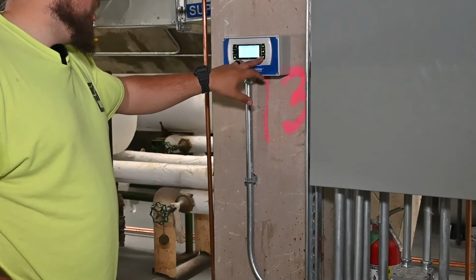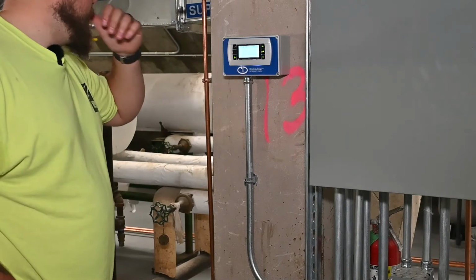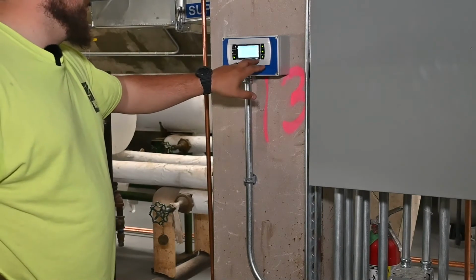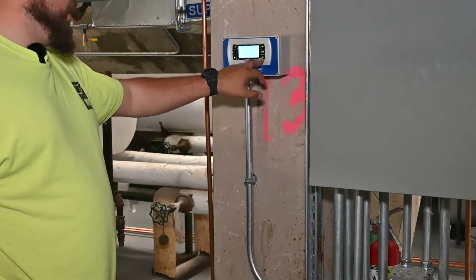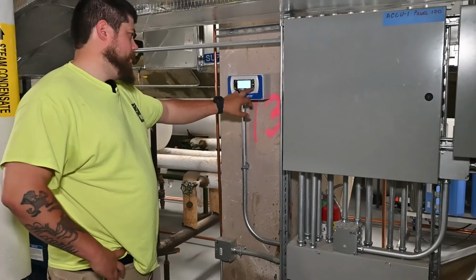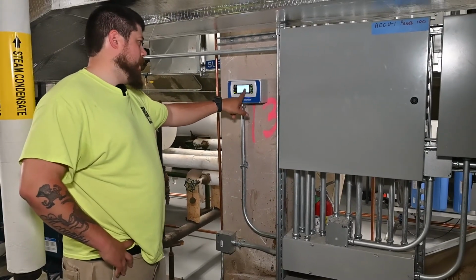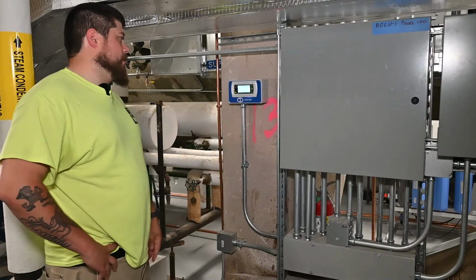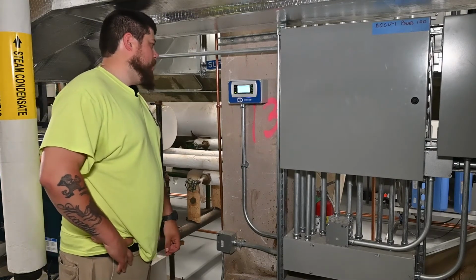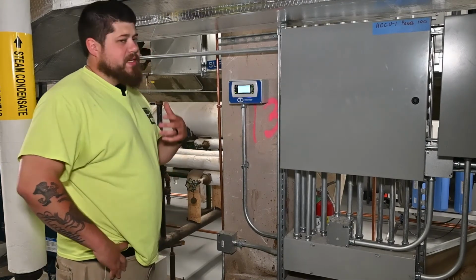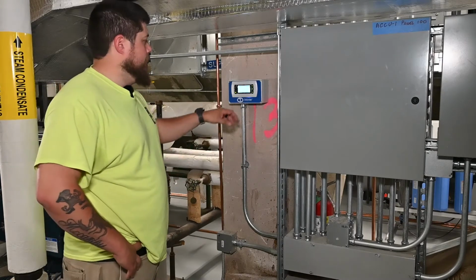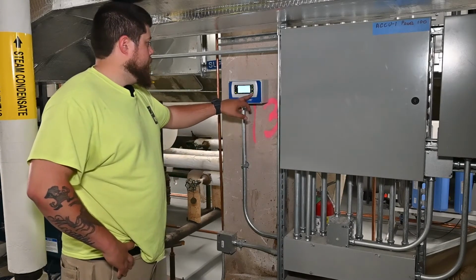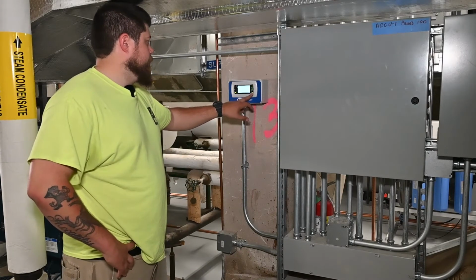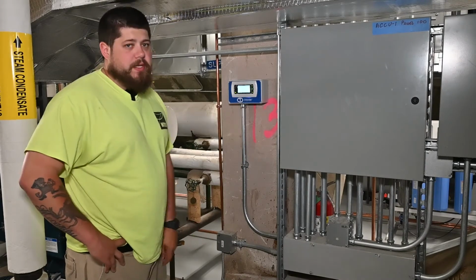It can tell you what the call is for the unit itself, whether it wants dehumidification, whether the flow is running, whether the return's running, the wheel's running, any of that good stuff. It also has a limit here to show you the runtime. It'll tell you how many hours it's been running, which is somewhat nice because you can eventually base your PMing off of the runtime. And that's it. Pretty easy controller.